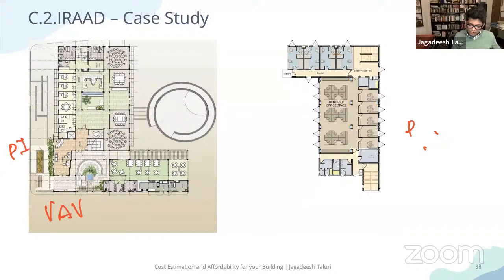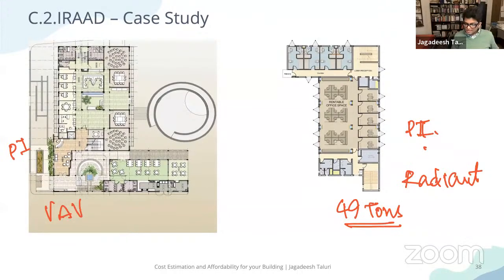When they were constructing phase two, that's when Ashok Lal and team tried to bring in little better consultants or new experts, and they explored what if we go to a radiant system. They designed this whole building for radiant, and said this requires 49 tons of cooling. When it came to ordering the chillers, the same consultant who had done the energy modeling for phase one also looked at the existing energy bills and saw that the actual peak load of the phase one building is 91 tons.